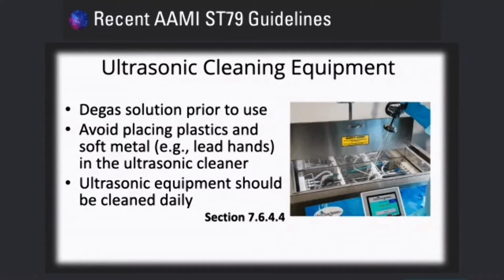Degas your solution prior to use. Degassing allows the gas that's dissolved in the water to be eliminated, and it makes the water more solid, so the cavitation process can be more effective. All of our machines do that automatically for you. Avoid placing plastics and soft metals like lead hands in the ultrasonic cleaner. For one, they might not do any good, or two, depending on the actual material and how soft it is, they might deteriorate, and other contaminants might leach off of your instruments and affect others.